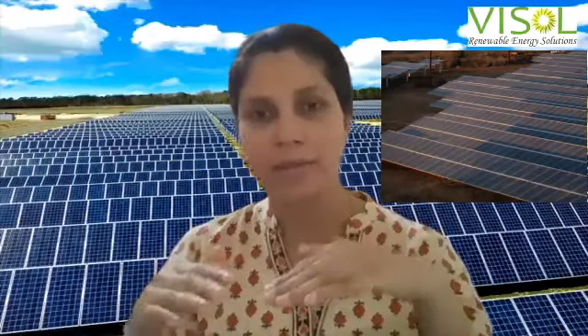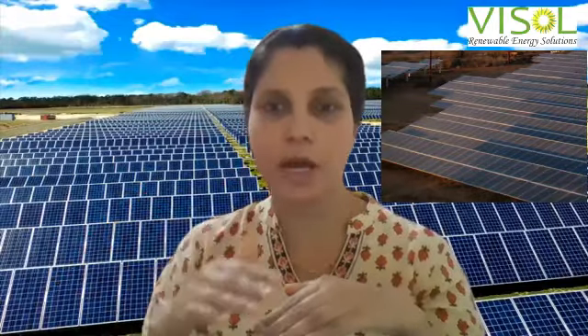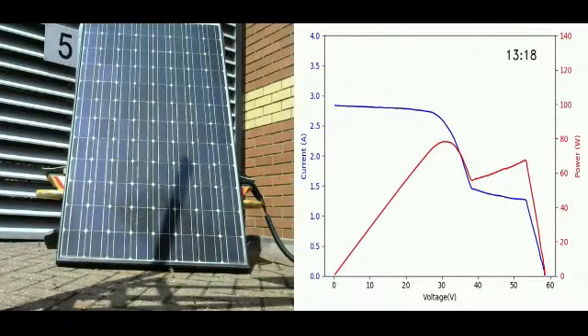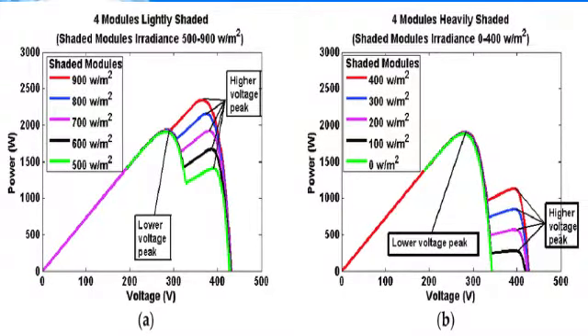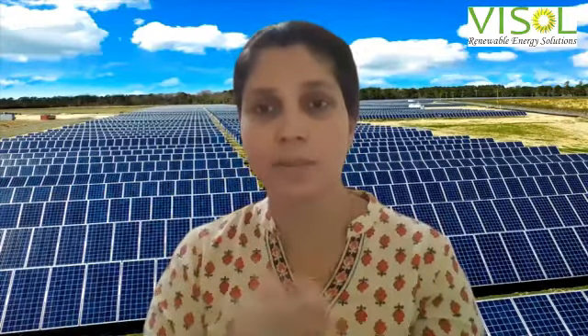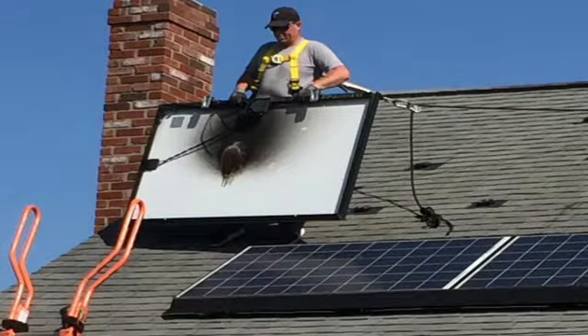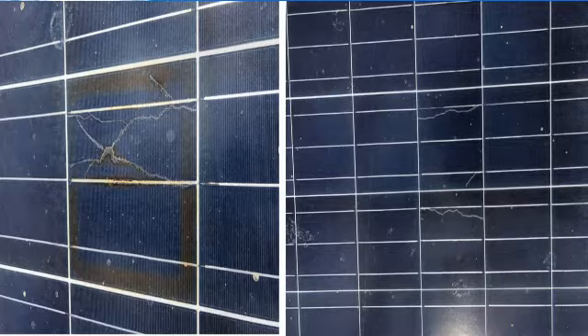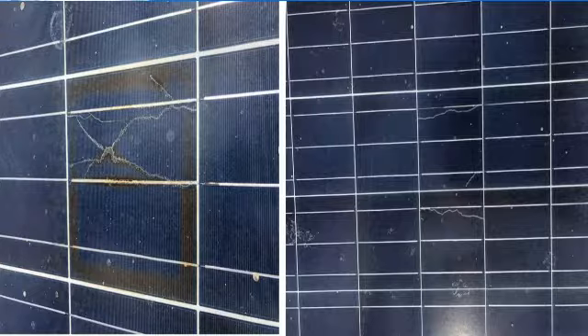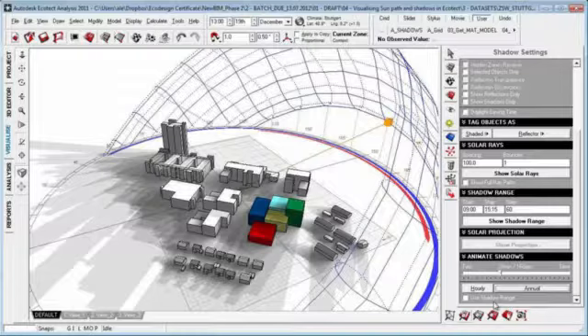If the solar panels are placed under shadow, the performance of the entire solar PV plant goes down. Solar panels are mostly arranged in strings to meet the voltage requirements. A shade on one panel not only reduces the efficiency of that panel but also cuts short the supply from the entire string. Eventually, the panel gets damaged due to heating. Therefore, a proper shadow analysis with specialized software is very important to design a solar power plant.